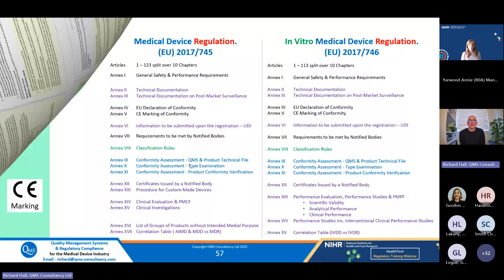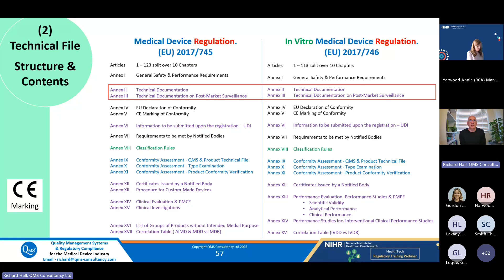So if you look in Annex 2 of either the medical device regulation or the in vitro medical device regulation in Europe, it now tells you. Annex 2 has a description of what's needed in a medical device technical file, and it says you must have 6 folders within your technical file. So device description and specification, information supplied by the manufacturer, that's things like the instructions for use. Design and manufacturing information is information that tells the reader of the technical file who designed and manufactured the device and what the processes were.